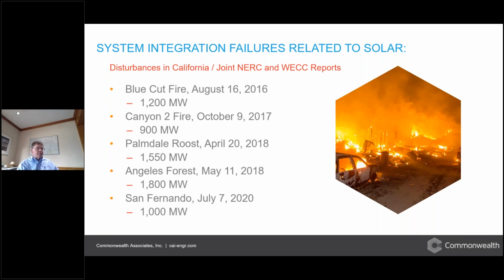Now, in these incidents that are listed here, most all of them are transmission-related faults. You've got faults on 500 kV transmission, other 220 kV transmission systems. And then you have a solar facility that's located hundreds of miles away that trips due to the normal clearing of faults on the system. So Blue Cut Fire, that was 1,200 megawatts. That happened back in 2016. That's a picture there of the carnage of that fire, just east of Los Angeles.